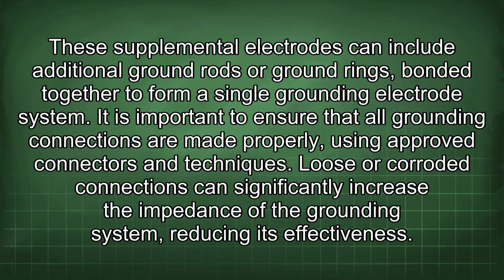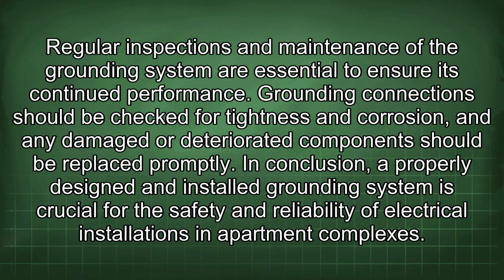Loose or corroded connections can significantly increase the impedance of the grounding system, reducing its effectiveness. Regular inspections and maintenance of the grounding system are essential to ensure its continued performance. Grounding connections should be checked for tightness and corrosion, and any damaged or deteriorated component should be replaced promptly.